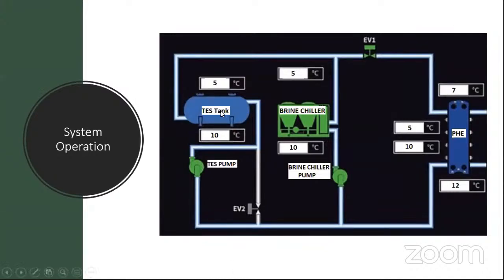See, we have our thermal storage tank here, we have our brine chiller here, and we have our PHE here, and these are pumps, and these are pipes, and inside the pipes, inside the system, is our monoethylene glycol solution, or either monoethylene or propylene, depending upon the application. Sometimes in some food applications, propylene glycol is also used, but generally for comfort cooling applications, monoethylene glycol is very popular. So this is the schematic here.